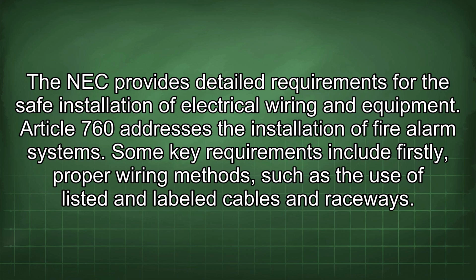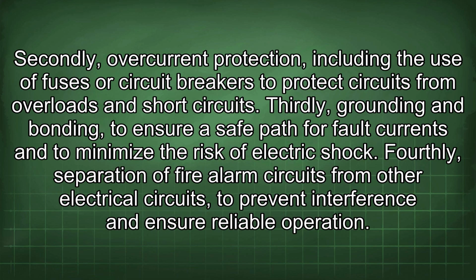Some key requirements include: firstly, proper wiring methods, such as the use of listed and labeled cables and raceways. Secondly, overcurrent protection, including the use of fuses or circuit breakers to protect circuits from overloads and short circuits. Thirdly, grounding and bonding, to ensure a safe path for fault currents and to minimize the risk of electric shock. Fourthly, separation of fire alarm circuits from other electrical circuits to prevent interference and ensure reliable operation.